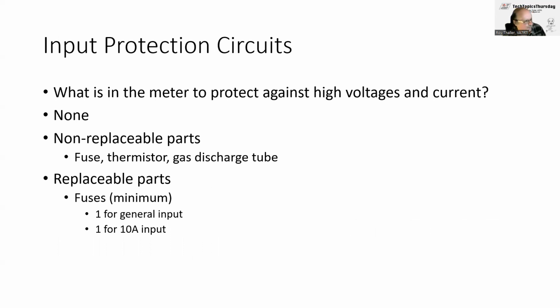Input protection circuit. See what your meter has. It can have no protection. It could have some non-replaceable parts, like a fuse, or a thermistor or a gas discharge tube, and these generally cannot be replaced. The thermistor and the gas discharge tube are designed to protect you, and they're built into the meter. Some meters have an internal fuse that you can't replace, so if the fuse goes, you'd probably have to throw the meter away. Now, most meters will have some fuses, one fuse for the general input, which will probably be like a 200 or 300 milliamp fuse, and then a 10 amp fuse for your 10 amp input. But this may not always be the case.